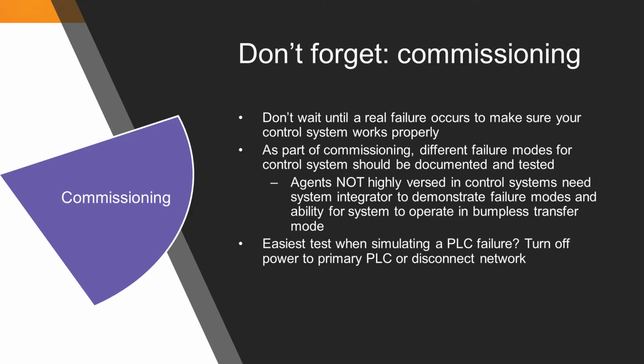As we went through the process of recommissioning the SCADA system, the owner took the opportunity to do a complete test of the redundancy. That meant, in addition to going through a series of tests to identify the operating and failure modes of the generators or other components such as the transfer switches, they did a full pull-the-plug test where they simulated the loss of utility power to the building.